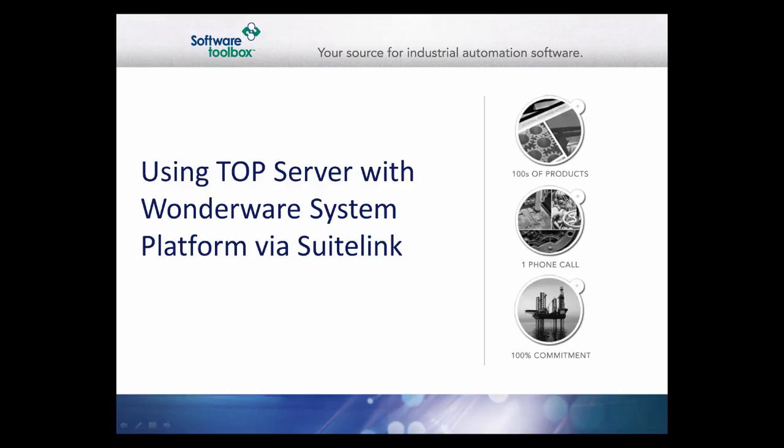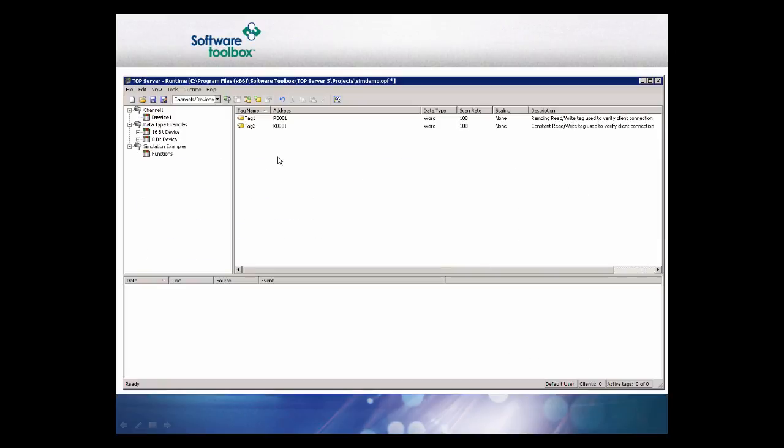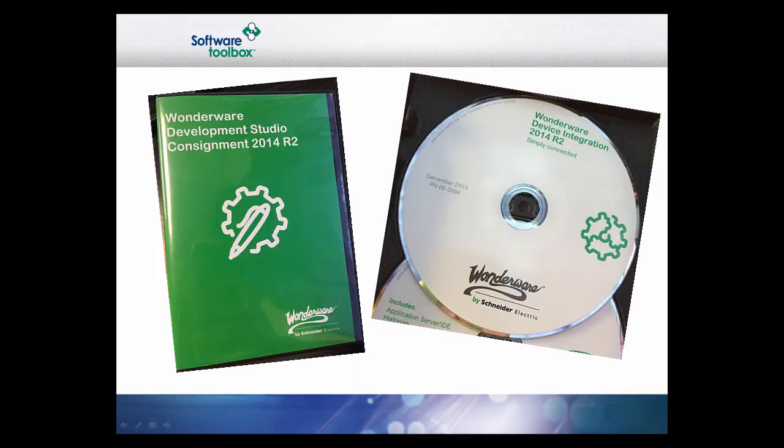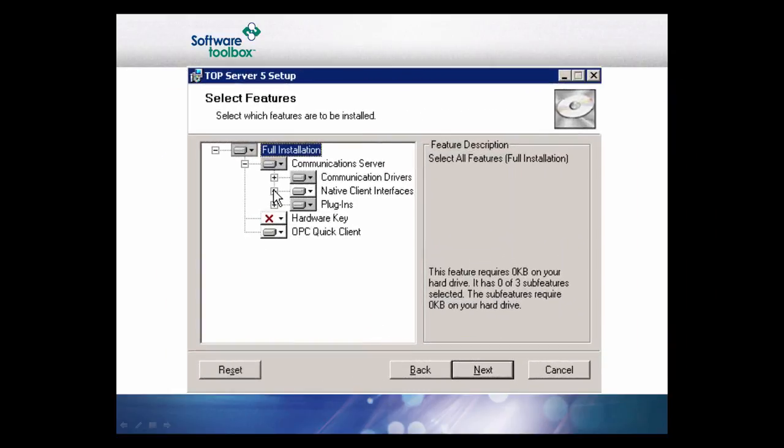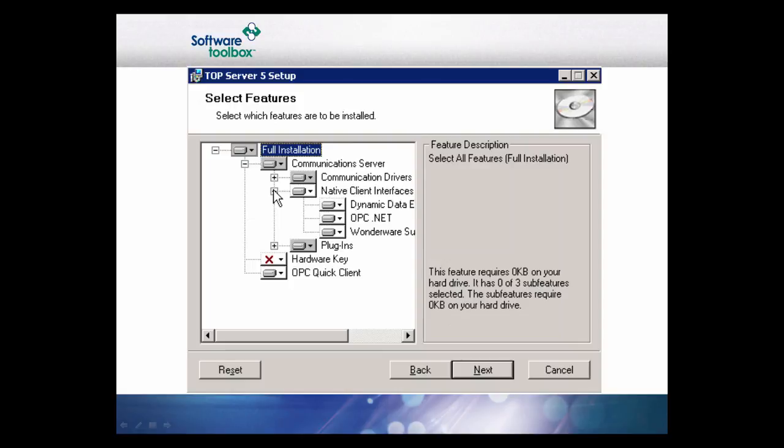In this example, we will use the simulation project that installs with TopServer. In order for the TopServer to allow SuiteLink connections, the Wonderware common components must be installed on the machine before the TopServer software. The common components can be installed from the Wonderware Factory Suite IO Server Installation CD. In many existing installations, the necessary files will be present already. However, this may not be the case if the system platform resides on a remote machine.